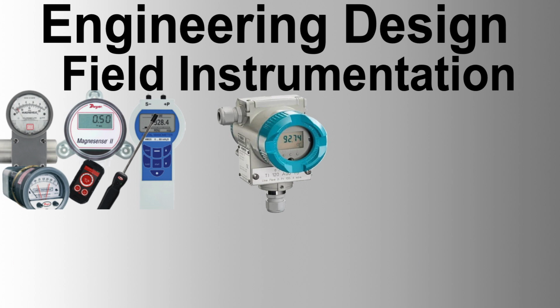Safety instruments. Safety-related instruments should comply with specific safety standards and have self-diagnostic capabilities. SIL 1 and higher initiators should have their own independent process tappings, impulse lines, sensors, utilities, etc. Intelligent sensors with 4 to 20 milliamps output signals are preferred for their lower failure rates and better accuracy. Accessibility. Instruments must be located for easy access and maintenance, following minimum accessibility requirements for operational attention or maintenance.